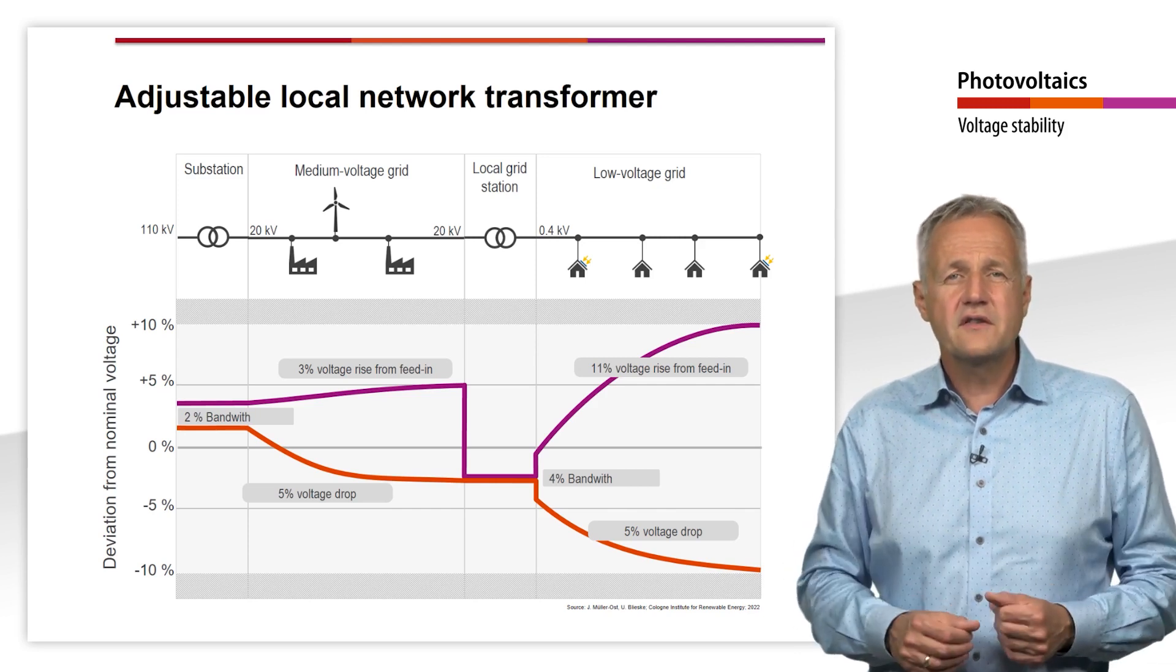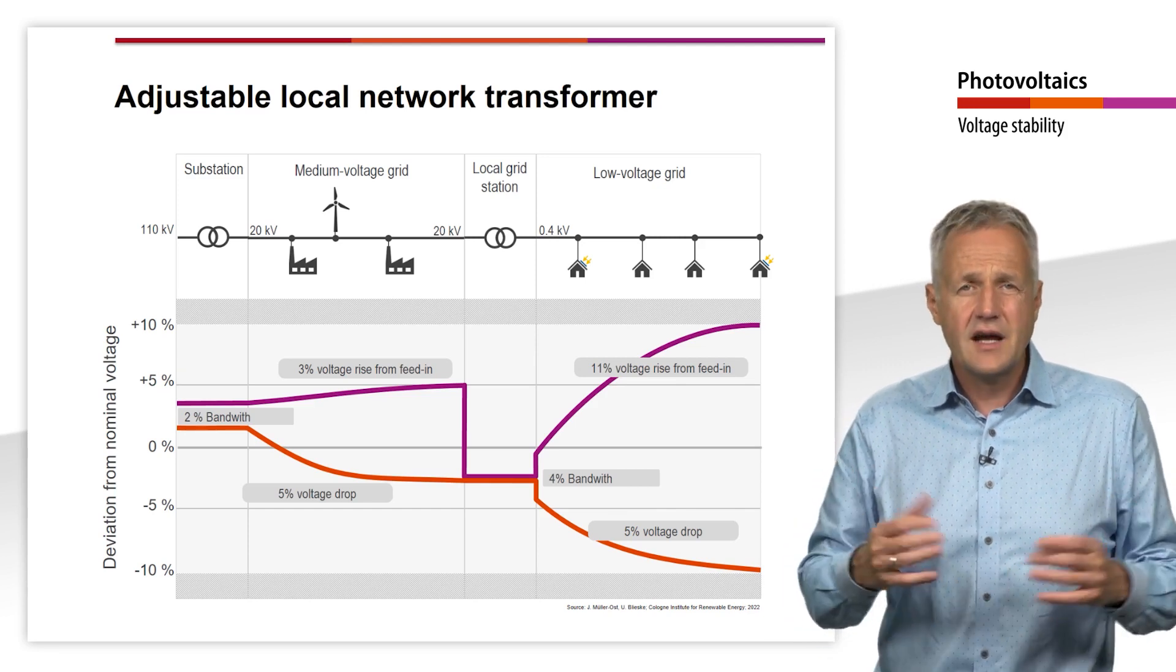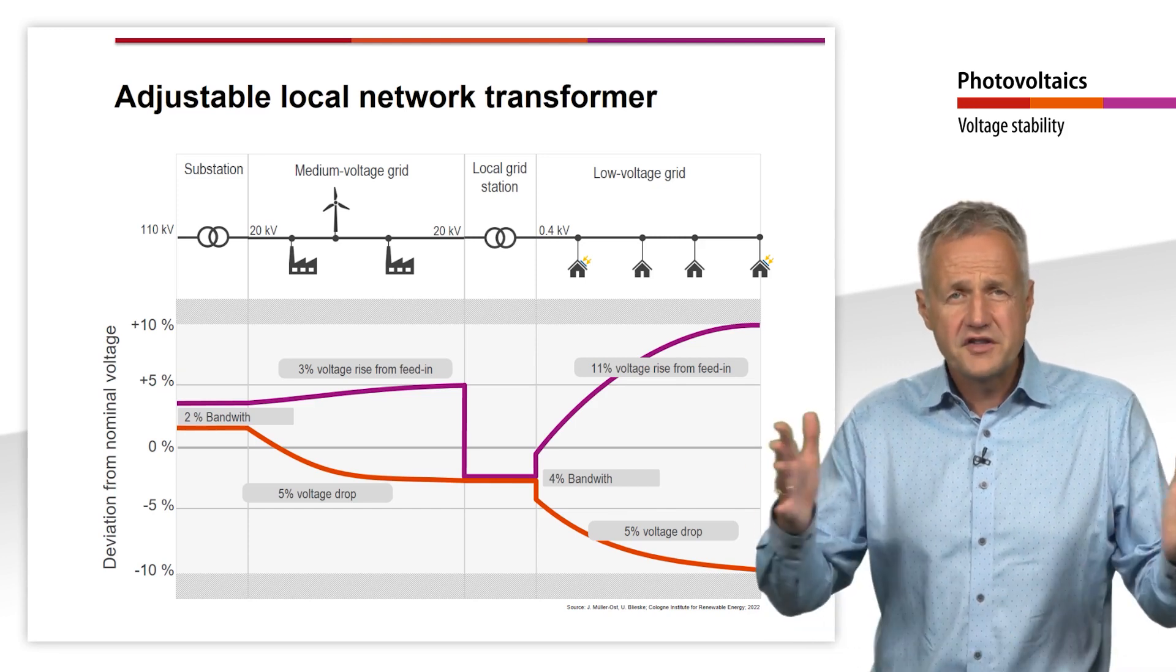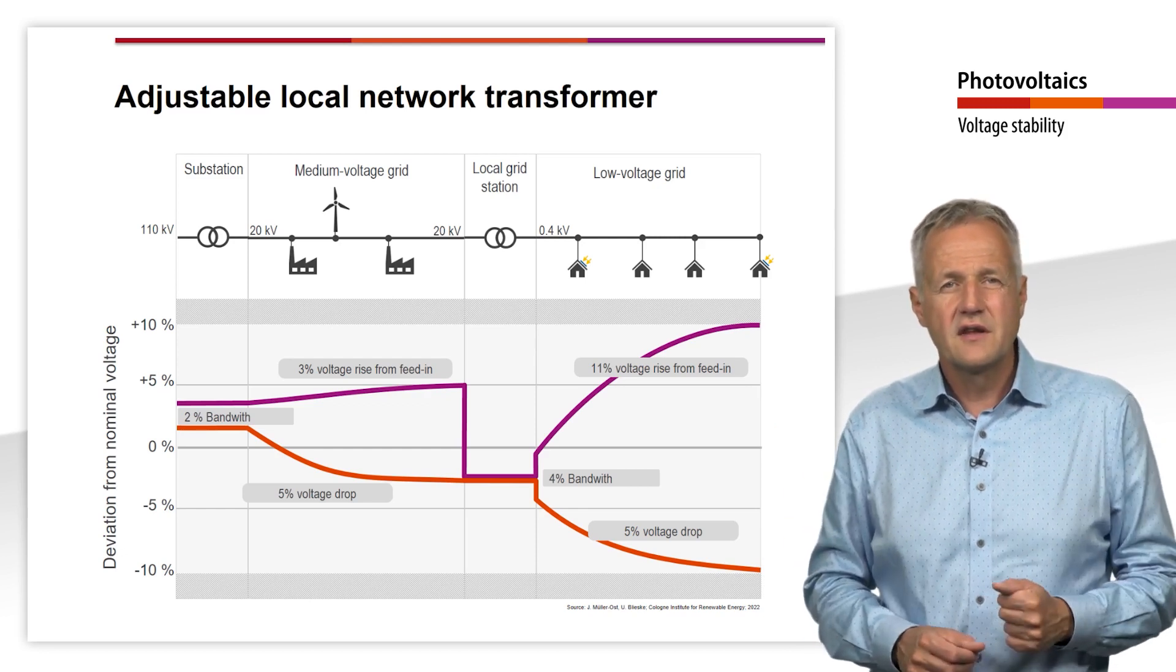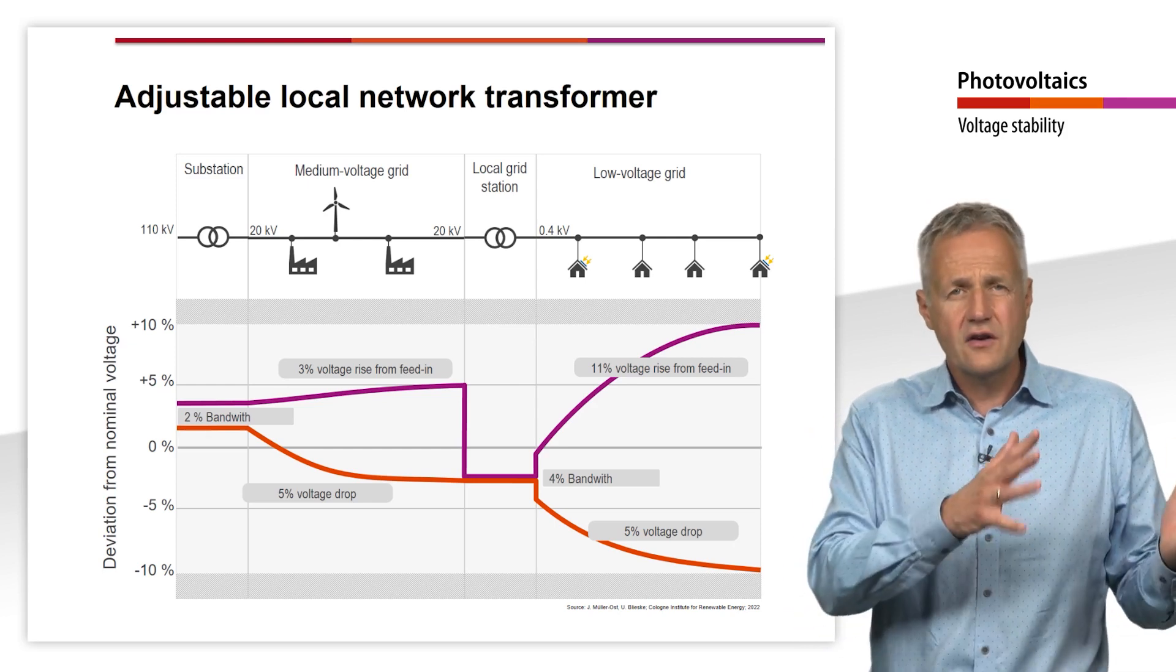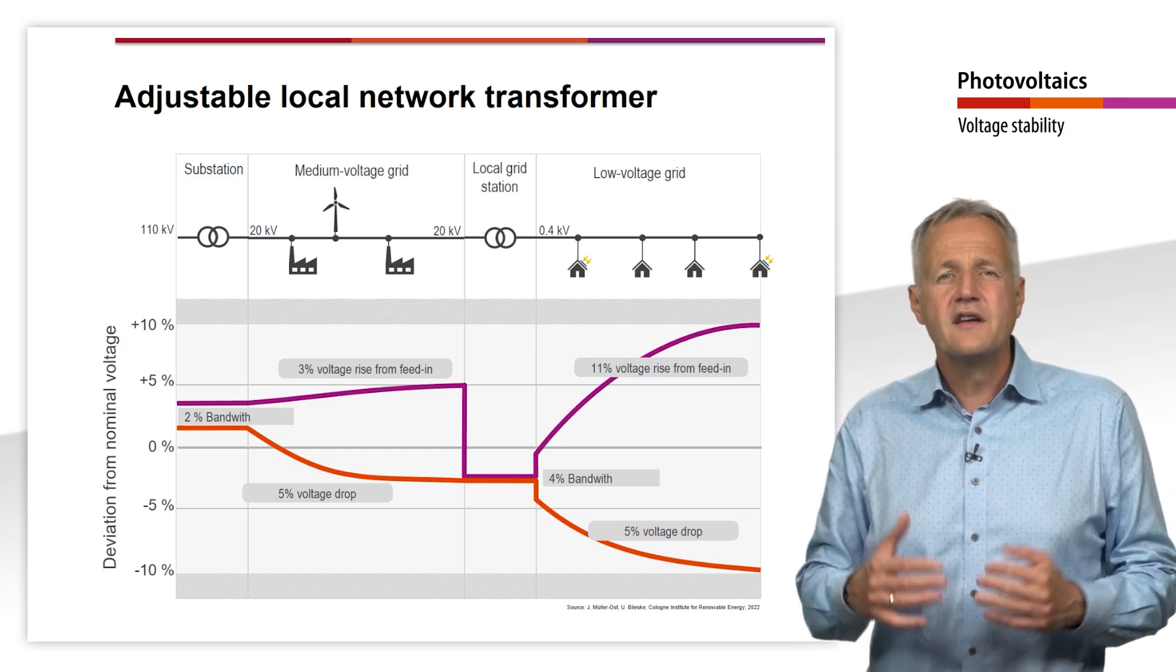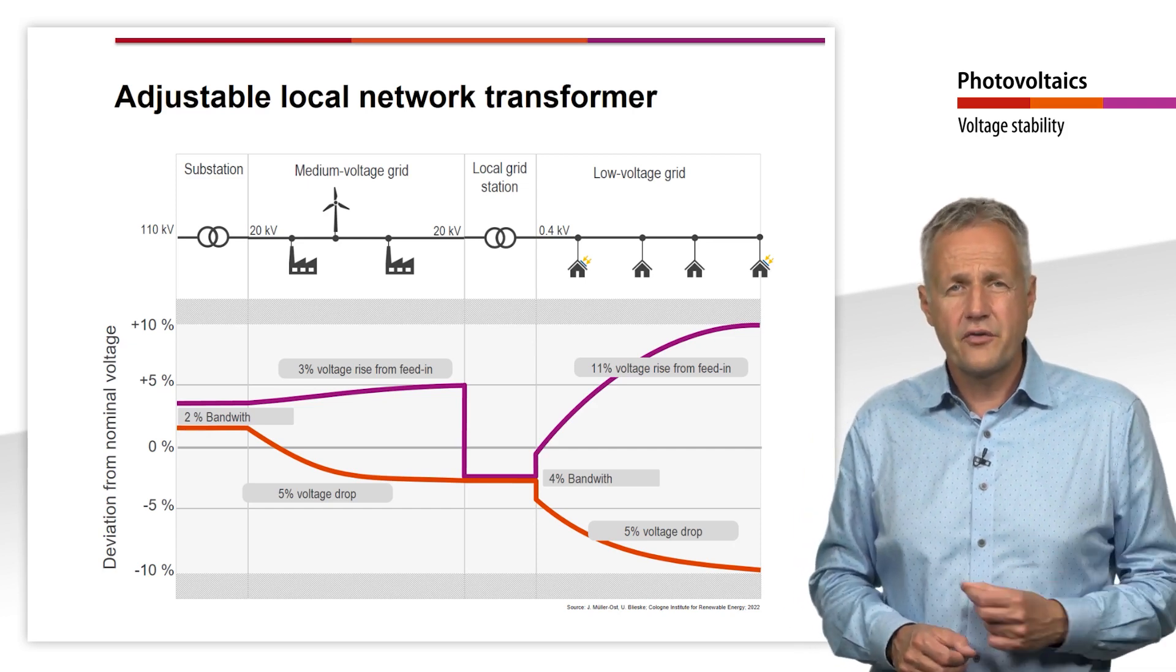This allows the voltages between the medium voltage and the low voltage grids to be decoupled so that a wider voltage band is available for feed-in at both grid levels. The decision to expand the lines or replace the local network transformer is essentially an economic one, made and borne by the grid operator.